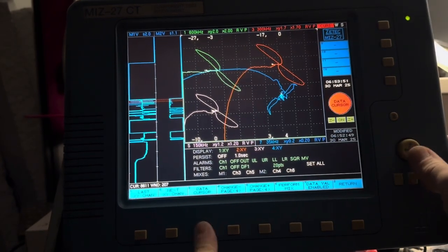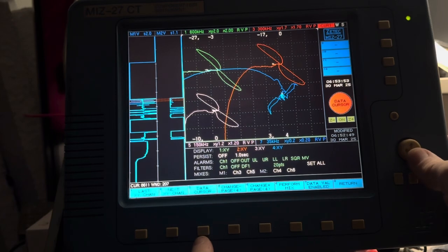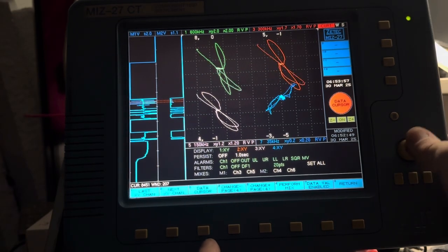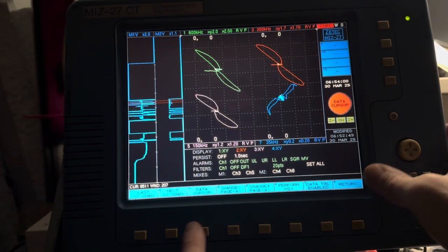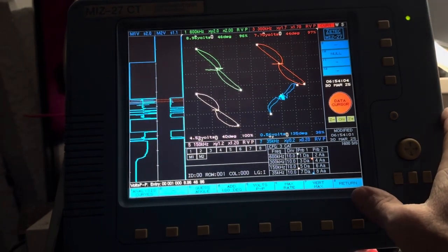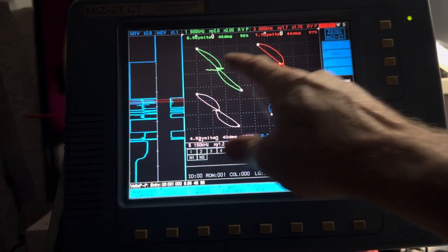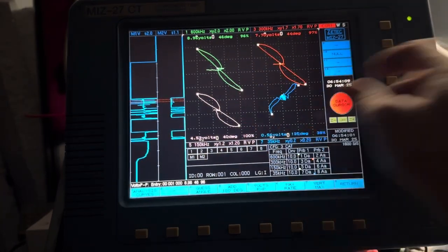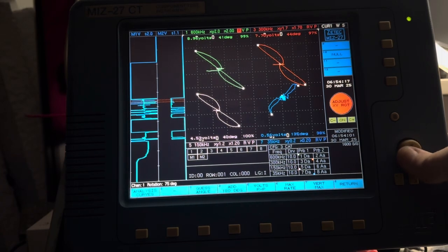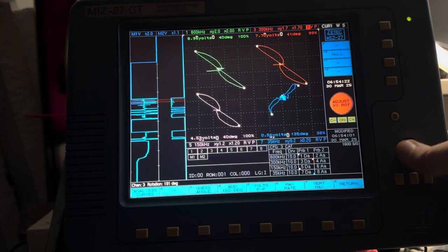So to show you what I mean, let's go to the 80% flaw. All of those have different phase angles. If you want me to prove it, I will. We're going to go to measure and we're going to hit peak to peak. There we got 46 degrees, 44 degrees, and 40 degrees. All right, let's do a little trial and error here. We're just going to set them exactly the same because typically you set them all to 40. So let's get precise because I know you like precise.